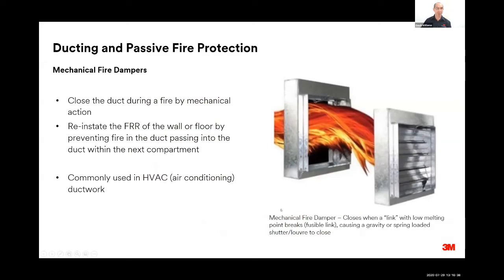Mechanical dampers, mechanical fire dampers, work by closing the internal sections of the duct through a mechanical means. So in the instance a fire breaks out, heat, for example, may melt or damage a link that then allows, through gravity or spring, a shutter or louver to close, effectively shutting the duct to the flow of gases and fire. So if fire breaks into the duct within an affected compartment, then it can't move through to the next compartment. So the fire resistance rating of that wall or floor is restored through that fire damper. And that's commonly a method used for heating, ventilation and air conditioning ductwork.